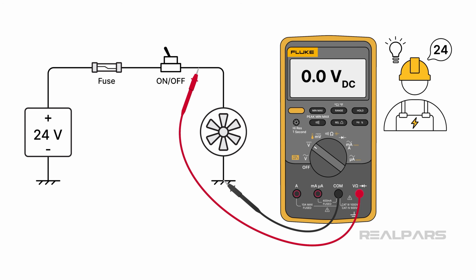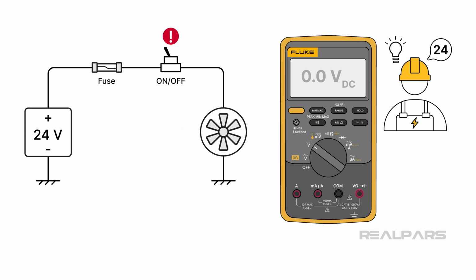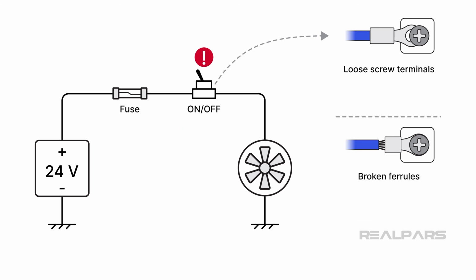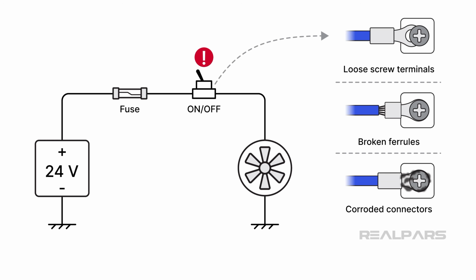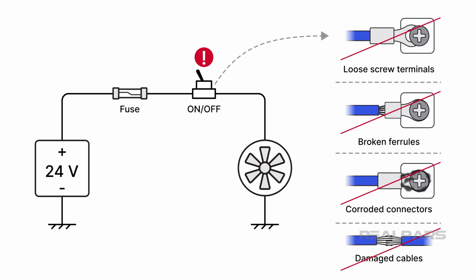Principle 7. Verify before replacing. Victory! You think you found the faulty culprit. Not so fast. Always verify the surrounding wiring before replacing the suspected bad component unless it's blatantly obvious. Take a few minutes to check for loose screw terminals, broken ferrules, corroded connectors, and damaged cables. You might fix the problem by tightening the wire during reassembly. Prove the component itself is rightfully destined for the garbage before you replace it with a new one.